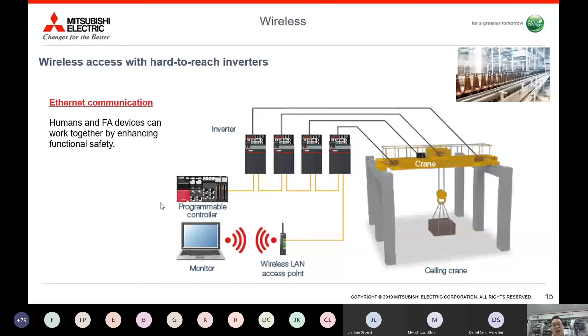Next point on the smart functions: even if the inverters are located in a high place, as you can see in this application of ceiling crane control, the inverters are located at a very high position. You can use wireless access to make adjustments to the inverter parameters and for inverter monitoring. Simultaneous monitoring of multiple axes is possible, and inverter maintenance such as live diagnosis check is possible. The inverters can be connected to software in the monitor, and using a wireless LAN point, you can do the programming and monitoring at the computer side, enhancing functional safety between humans and the device.